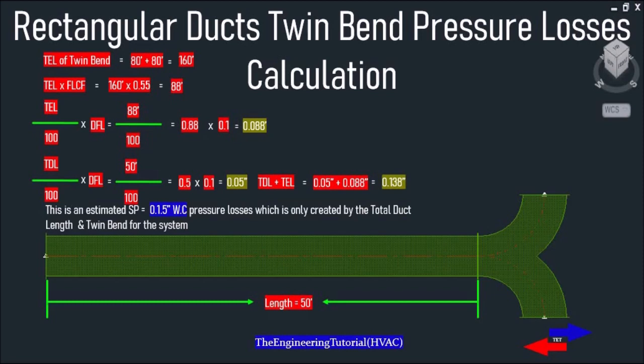We divide the total equivalent length of 88 feet by 100 and then multiply by a duct friction loss of 0.1, which comes out to 0.088 inch of water column. For the supply duct, we do the same calculation, which gives us 0.05 inch of water column. Finally, total duct length plus total equivalent length gives us 0.138 inch of water column — approximately 0.15 inch of water column.